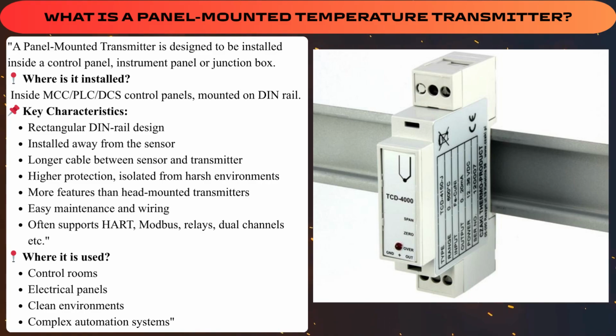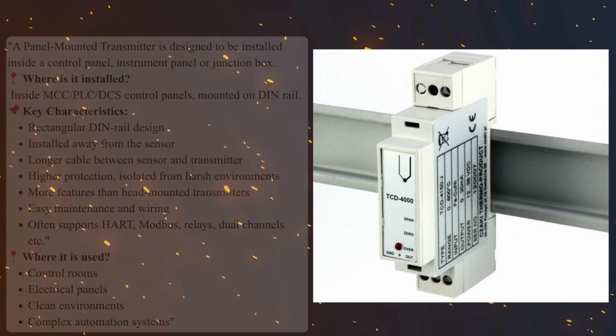Longer cable between sensor and transmitter. Higher protection, isolated from harsh environments. More features than head-mounted transmitters. Easy maintenance and wiring. Often supports HART, Modbus, relays, dual channels, etc. Where is it used? Control rooms. Electrical panels. Clean environments. Complex automation systems.